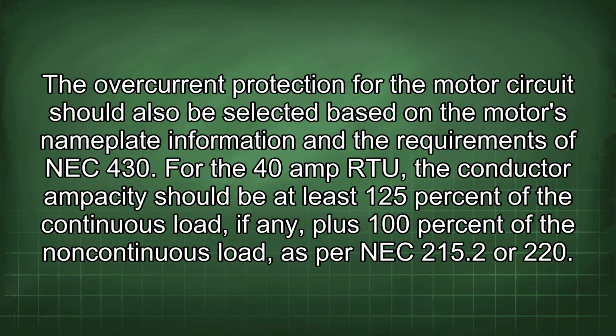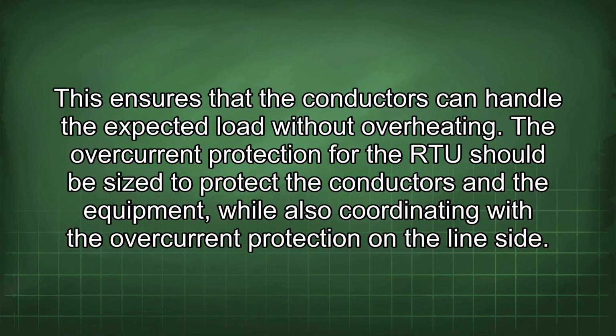The overcurrent protection for the motor circuit should also be selected based on the motor's nameplate information and the requirements of NEC 430. For the 40 amp RTU, the conductor ampacity should be at least 125% of the continuous load, if any, plus 100% of the non-continuous load, as per NEC 215.2 or 220. This ensures that the conductors can handle the expected load without overheating. The overcurrent protection for the RTU should be sized to protect the conductors and the equipment, while also coordinating with the overcurrent protection on the line side.